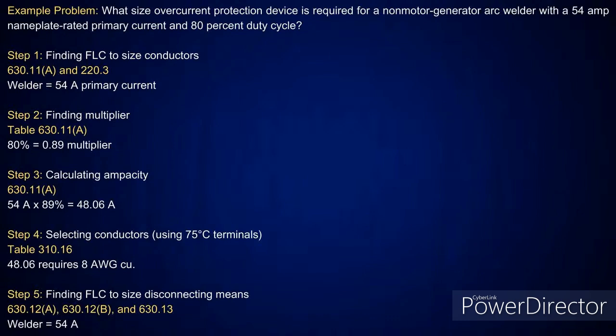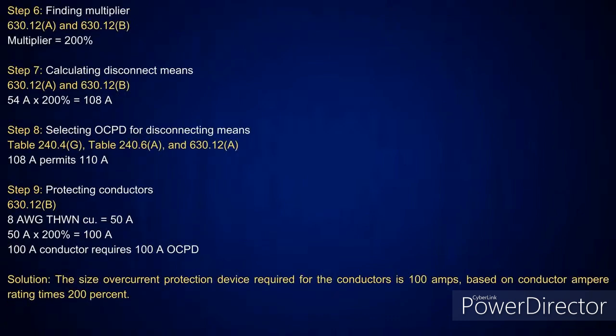Now I'm going to look at sizing the overcurrent protection device. I'm still going to use the nameplate of 54 amps. And then I'm going to look at 630.12A, and you look at 12B, it all ties in the same there. It's going to tell you take it at 200%. So I take 54 amps at 200%, which gives me 108 amps. I can look at this two ways. I can say, all right, I'm going to protect the conductor at 110 amps, but I'm going to see if I could just do 100 amps. I can already tell you it is, because if I take 50 amps at 200%, what does it give me? 100 amps. See that?